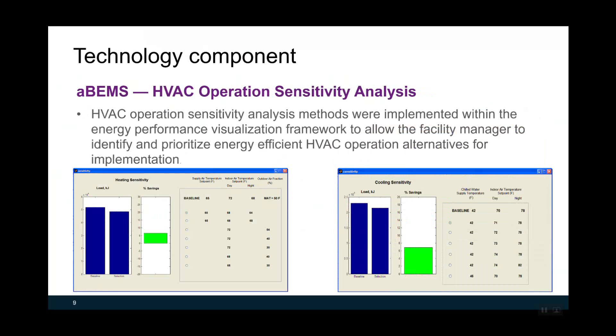For the HVAC operation sensitivity analysis, this analysis is implemented within the energy performance visualization framework to allow facility managers to identify and prioritize energy-efficient HVAC operation alternatives for implementation. The two figures on this slide show the operation sensitivity analysis for the supply air temperature setpoint and the chilled water supply temperature setpoint. Based on these sensitivity analyses, we gain better understanding of how supply air temperature and chilled water supply temperature setpoints impact energy consumption.